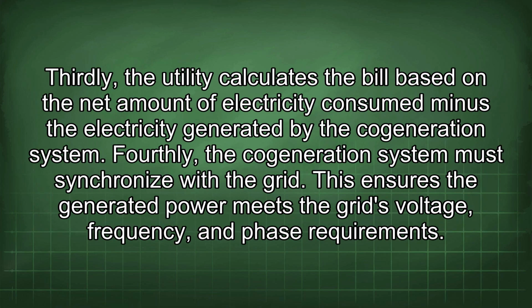Thirdly, the utility calculates the bill based on the net amount of electricity consumed minus the electricity generated by the cogeneration system. Fourthly, the cogeneration system must synchronize with the grid. This ensures the generated power meets the grid's voltage, frequency, and phase requirements.